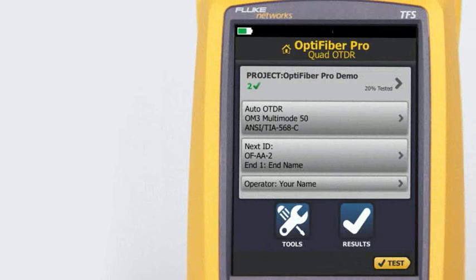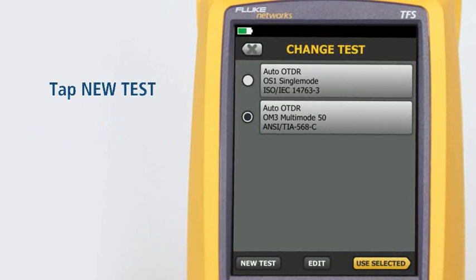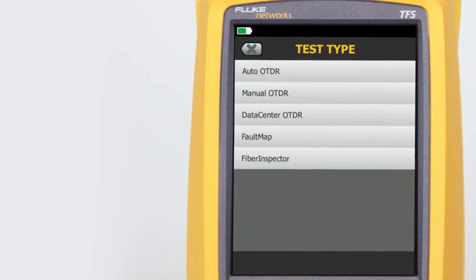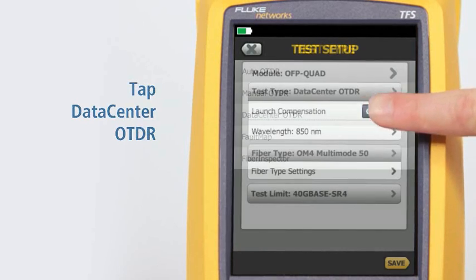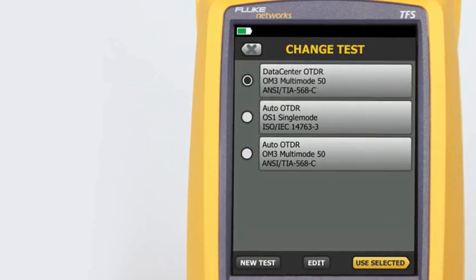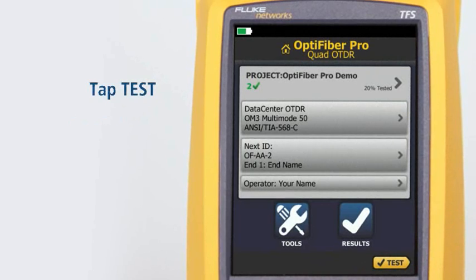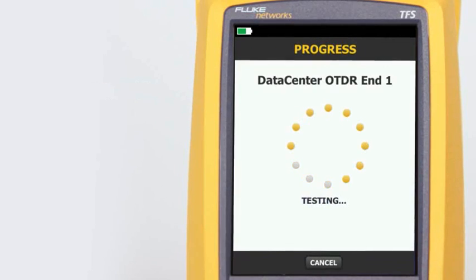The Data Center OTDR test mode is optimized for fiber installations that have short links, many connections, and the possibility of large reflections. Tap the Test Setup navigation panel, then tap New Test, then tap Data Center OTDR. Note that the Data Center OTDR defaults to only 850 nanometers for multi-mode fiber and 1310 nanometers for single-mode fiber — the wavelengths typically used in data centers. Tap Save, then tap Use Selected. We're now ready to run the test. Tap Test.